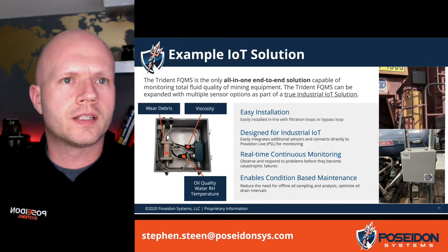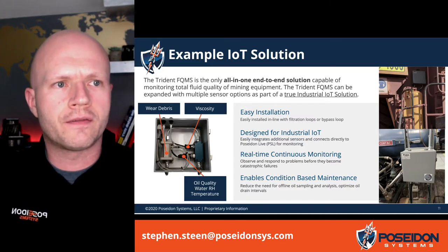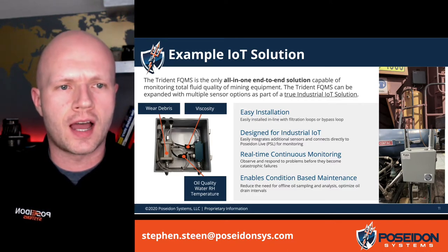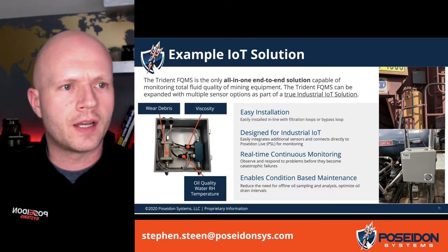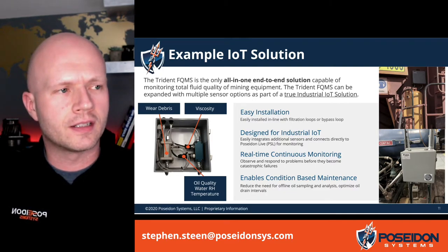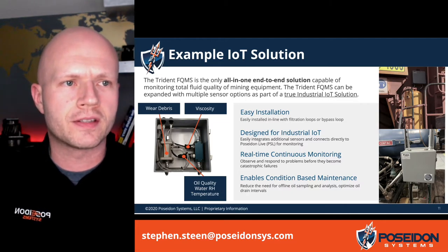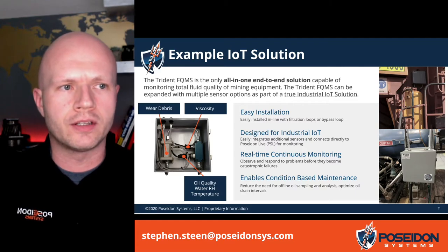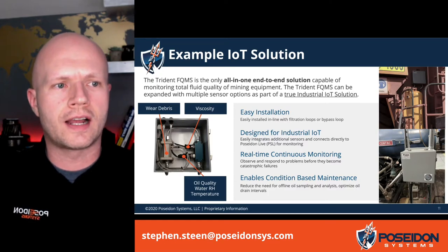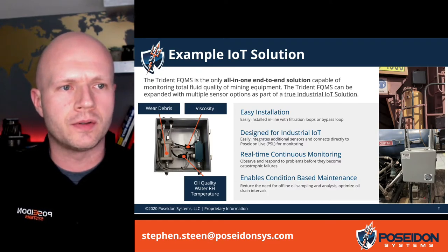I want to give you an example of what one of these solutions may look like. This is ours — we call it the FQMS, the Fluid Quality Monitoring System. You can see it comes with several sensors: a wear debris sensor, viscometer, oil quality sensor, and direct output of water relative humidity from the oil and temperature of the fluid. On the right hand side you can see a couple of examples — one is an installation on a haul truck, the other on a stationary piece of equipment. It's relatively easy to install, with one inlet and one outlet for fluid. It is designed for industrial IoT with a data logger and multiple ways of communicating back to the software, and can be integrated into your own data system while supporting continuous real-time monitoring.